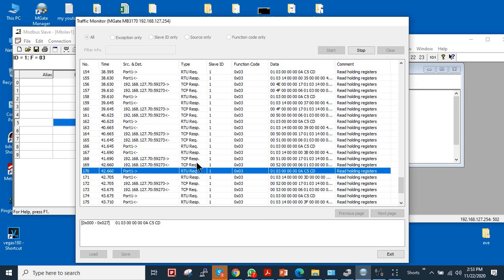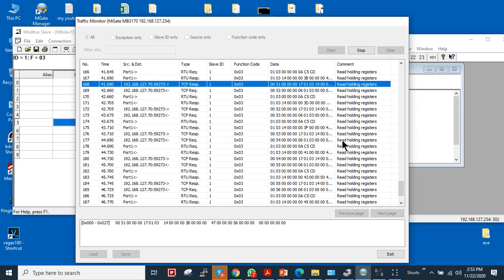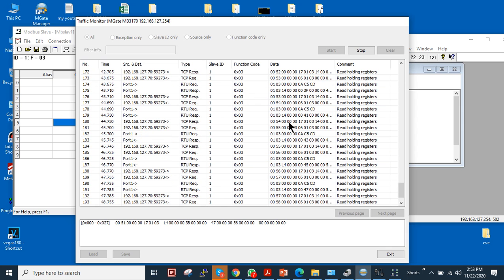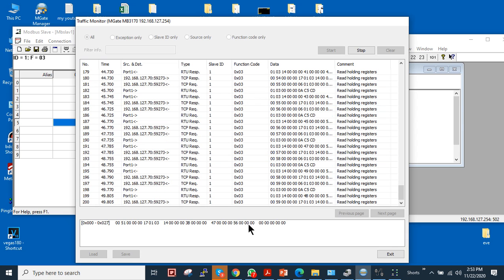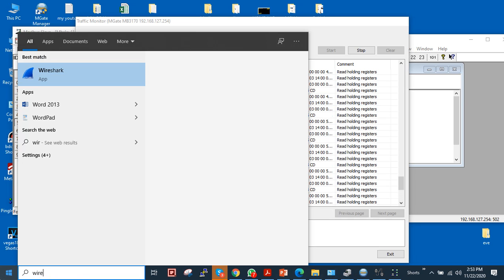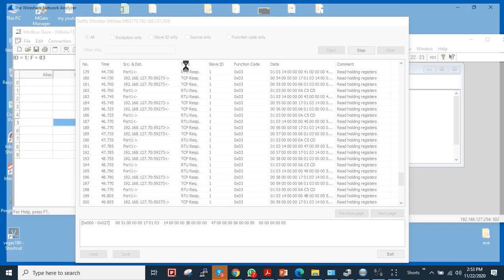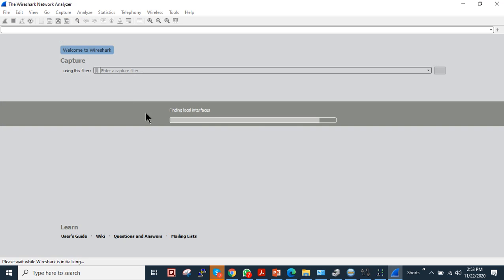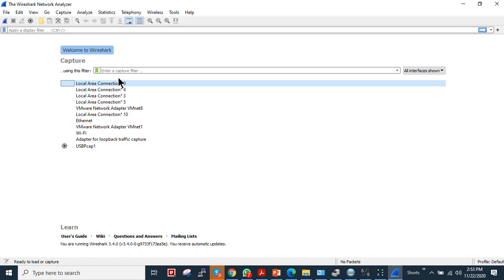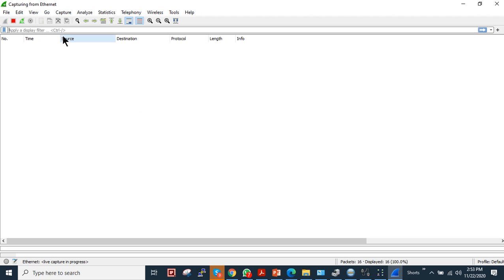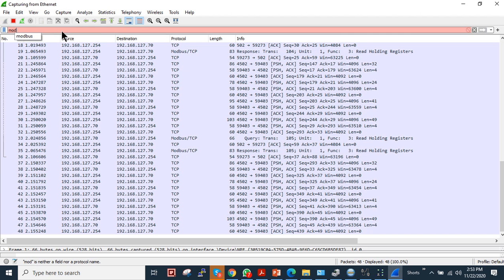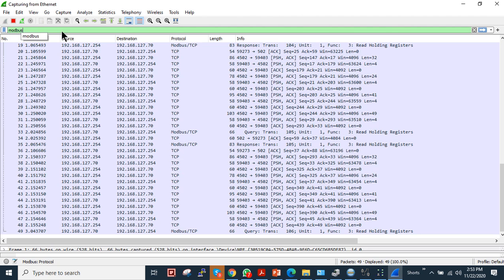If you see, I am having this value here in monitor mode. As you can see, the TCP request, response, everything is perfectly working fine. I will show you on Wireshark as well. Wireshark is a utility for traffic capture. Under Wireshark, I will capture the traffic for Ethernet and I will use the filter of Modbus.